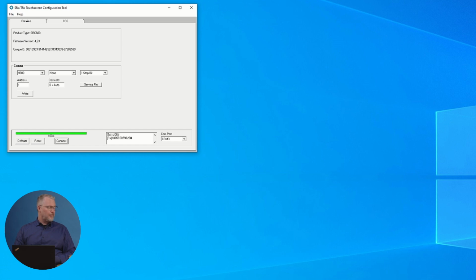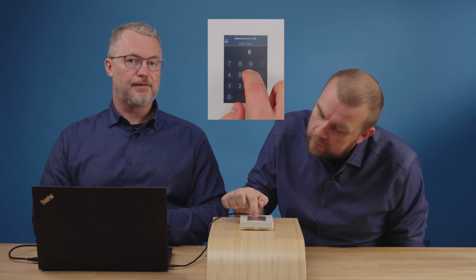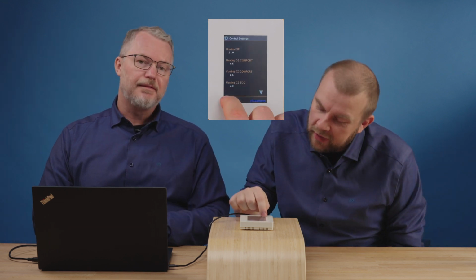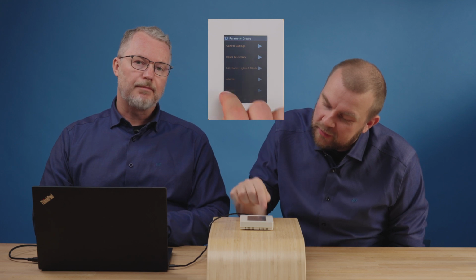Okay, now it's stored on your computer and is it so that you can use the same configuration with other TRCs? Exactly, so we can show an example. We can go into the configuration menu now on the same device and change the same parameter back to its standard setting, to 21 degrees instead. Okay. Sounds challenging for me, but I try. I think you're doing very good. Thank you. Now it's 21. And I now go like this and it makes the saving.